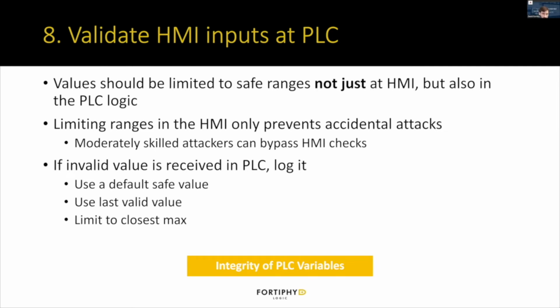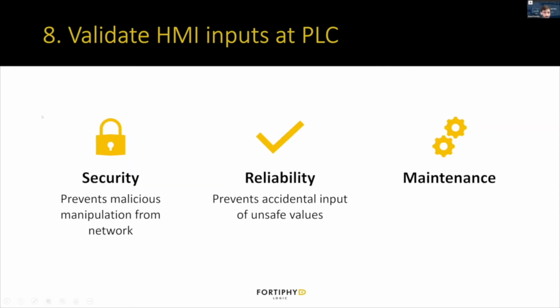You can approach this a couple of different ways. If an invalid value is received in the PLC, first of all, you do want to log it, to keep a record that we got a bad value here. We don't know if it's an accident or an attack, but just logging it can help with investigation to figure that out. When you get that value, you can choose to use a default safe value, use the last valid value you did receive, or limit it to the closest max or min within the safe range. For security, this helps prevent malicious manipulation from the network. For reliability, it helps prevent accidental input of unsafe values.